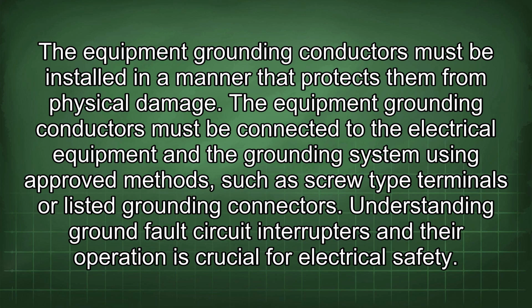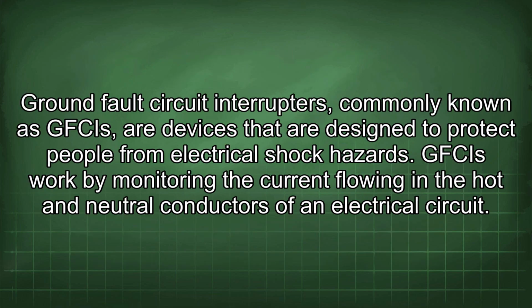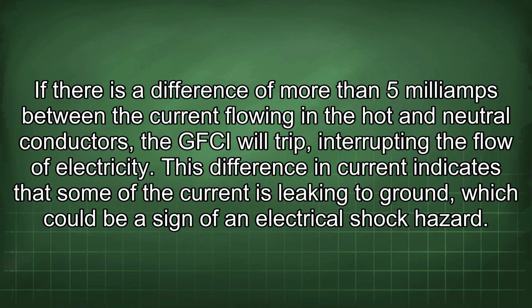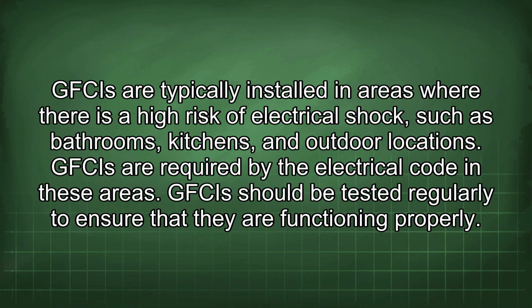Understanding ground fault circuit interrupters and their operation is crucial for electrical safety. Ground fault circuit interrupters, commonly known as GFCIs, are devices that are designed to protect people from electrical shock hazards. GFCIs work by monitoring the current flowing in the hot and neutral conductors of an electrical circuit. If there is a difference of more than 5 mA between the current flowing in the hot and neutral conductors, the GFCI will trip, interrupting the flow of electricity. This difference in current indicates that some of the current is leaking to ground, which could be a sign of an electrical shock hazard. GFCIs are typically installed in areas where there is a high risk of electrical shock, such as bathrooms, kitchens, and outdoor locations. GFCIs are required by the electrical code in these areas.